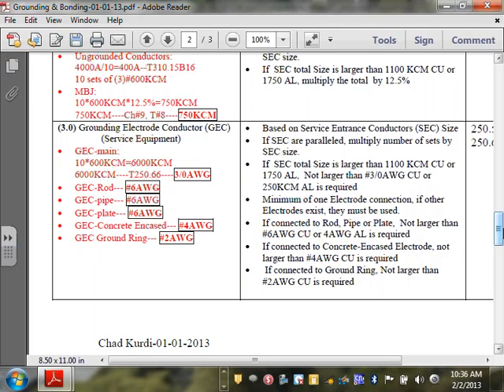You do the same thing, guys. Remember that magic number multiplication? Do the whole multiplication. You end up with 6,000 kcmil, go to 250.66, and you do not need to go larger than 3 aught. Does that make sense? No matter what you do, you don't have to go larger than 3 aught. Now, a lot of engineering firms, guys, they go bigger. They go 250 kcmil and 300 kcmil. But at minimum, you do not need more than 3 aught going into the switchgear.